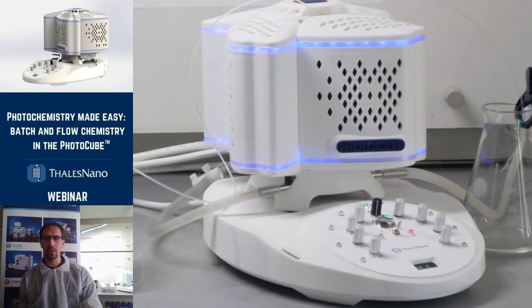Can we handle slurry material? In principle, yes, you can handle slurries. You just need to make sure that your slurry and also the pump which you use will be compatible with the tube size, so there will be no clogging. Most likely you need a peristaltic pump for flow applications. If you work in batch, in principle, slurries are not a problem.